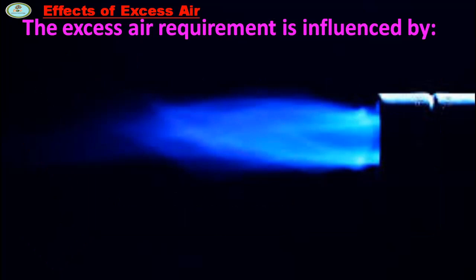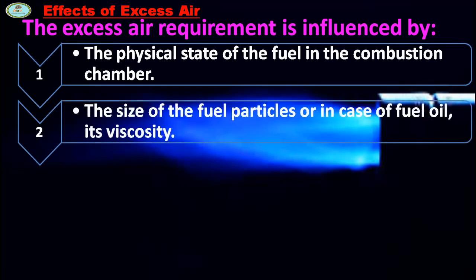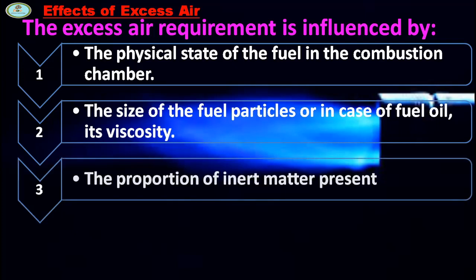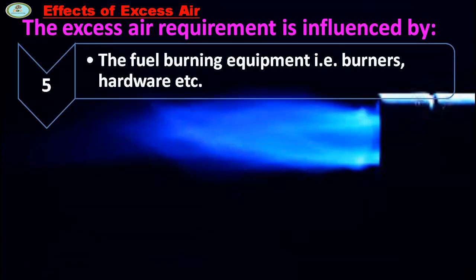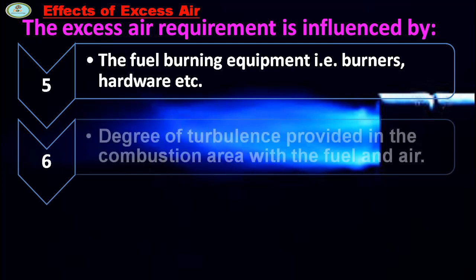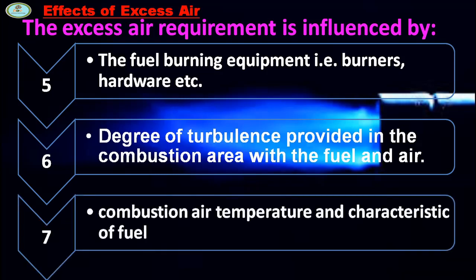The excess air requirement is influenced by the physical state of the fuel in combustion chamber, the size of the fuel particles or in case of fuel oil its viscosity, the proportion of inert matter present, the design of the furnace, the fuel burning equipment burners hardware, degree of turbulence provided in the combustion area with the fuel and air, combustion air temperature, and characteristics of fuel.